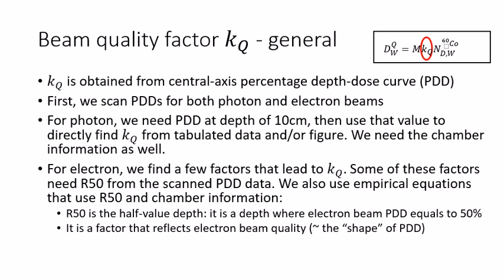For electron beam, we find a few factors that multiply together to equal KQ. Some of these factors need R50 value from the scanned PDD data. We will use empirical equations again that use the R50 and the chamber information to calculate those factors that eventually lead to KQ.